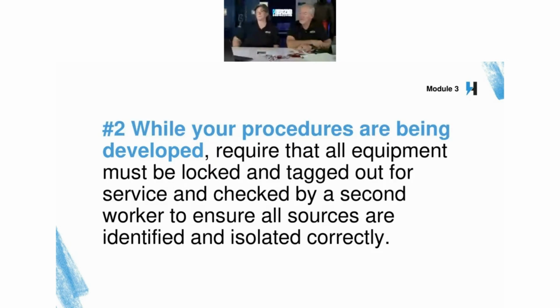Step 2, while your procedures are being developed, require that all equipment must be locked and tagged out for service and checked by a second worker to ensure all sources are identified and isolated correctly. To elaborate, if your procedures are not yet developed, you're in the process of doing so. Best practice is to make sure you are still locking out your equipment. Not having procedures is not an excuse. You still lock out your equipment, and have two authorized employees verify that everything has been locked out safely. It's a good step to take in that gap while you're getting your procedures written.